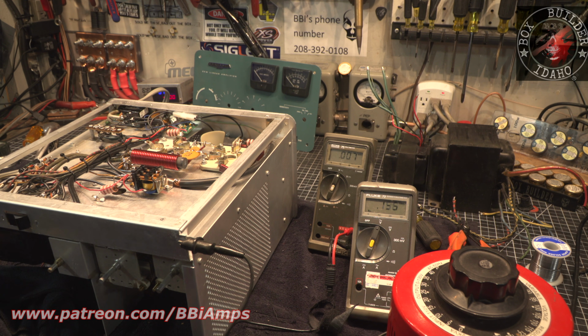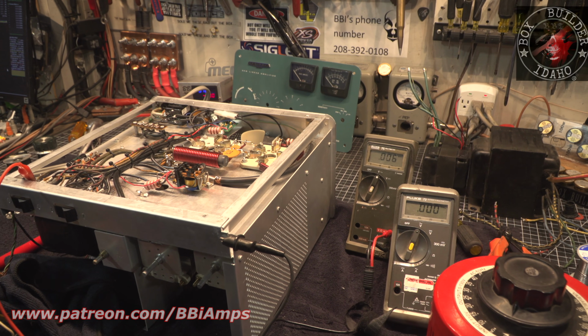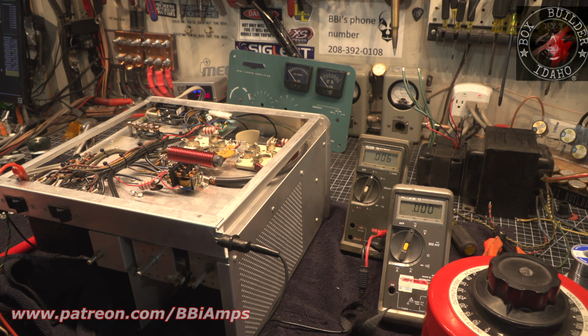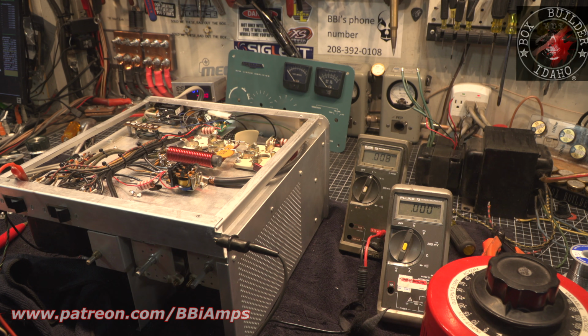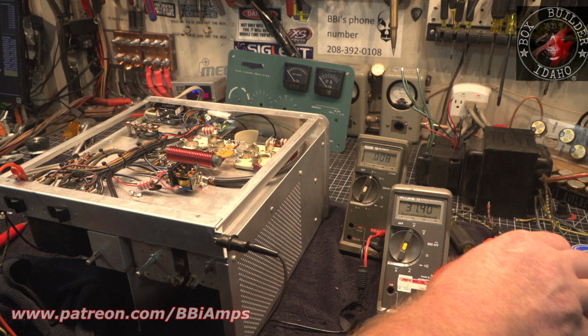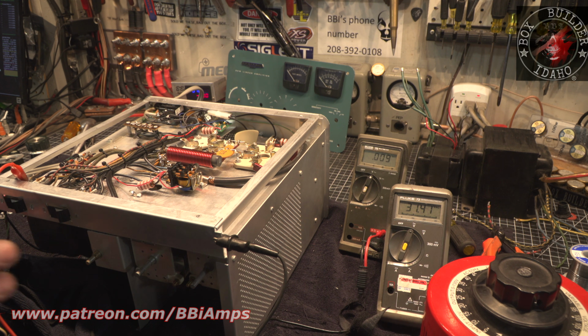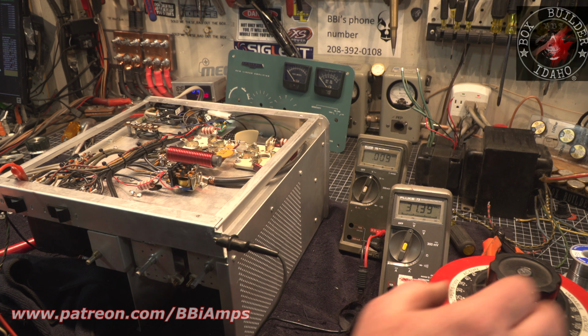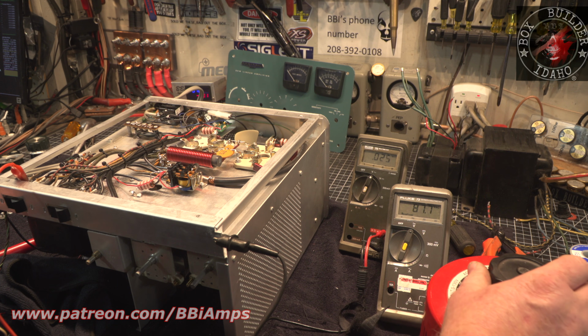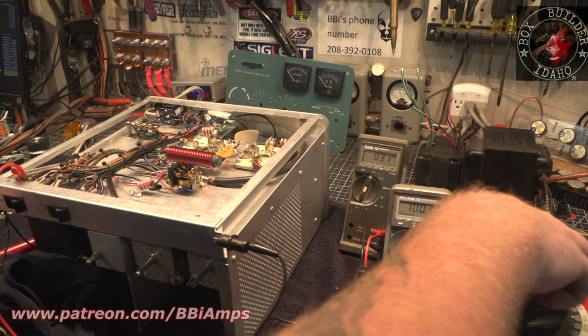See, look, we'll clip onto the primary side for the high voltage. Let me pan over here a little bit more. We'll come to the secondary. So this is our primary side. Check this out. Turn this on. So we'll put 31 volts in the transformer. Variac's not giving me any kind of resistance. And then we'll come over here and probe the secondary. We got nothing. It's trying. The transformer's trying. It's just like it's not completing this.